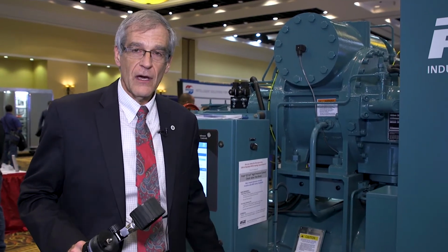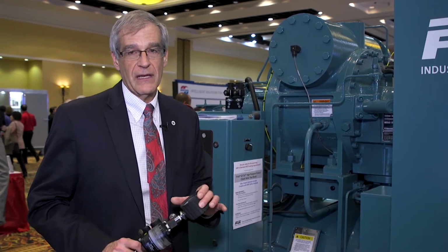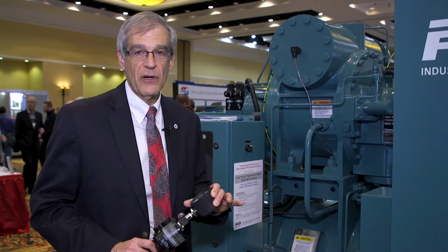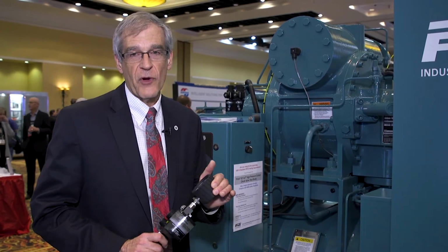The new standard that's coming out, IIAR 6, will require testing of this high pressure cutout every year. It has to be tested on a running compressor, and you have to demonstrate that it cuts out at the correct pressure with reference to a NIST traceable gauge.